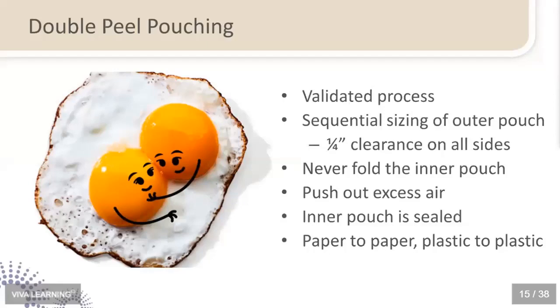Both pouches need to be sealed. The inner pouch must be sealed first, and you want to make sure that you've taken your hand to push out any of the excess air before you seal it and put it inside the outer pouch, because again, it could impact the sterilization process. You want to make sure in double pouching that you're doing paper to paper and plastic to plastic, so that you should be able to see the contents through the double pouching. You would not put it so that you see paper on both sides. So paper to paper, plastic to plastic.